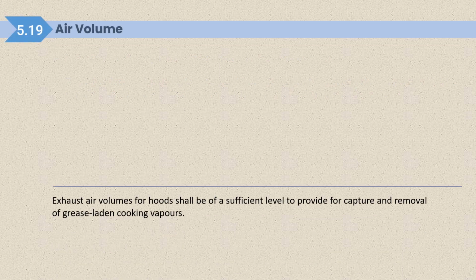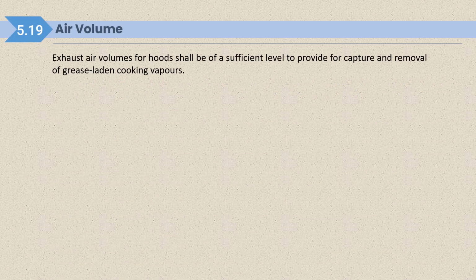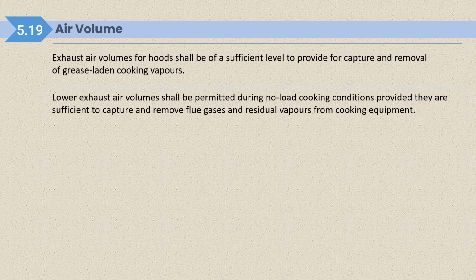Air volume, exhaust air volumes for hood shall be of sufficient level to provide for a capture and removal of grease-laden cooking vapors. Lower exhaust air volume shall be permitted during no load cooking condition provided they are sufficient to capture and remove flue gases and residual vapors from cooking equipment.